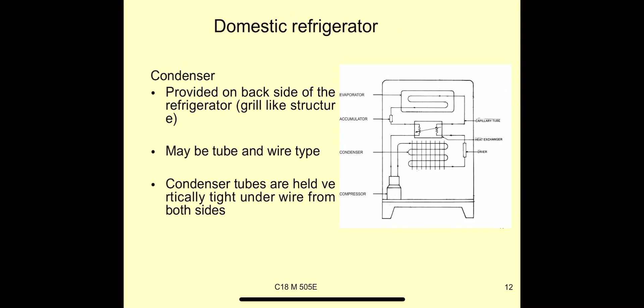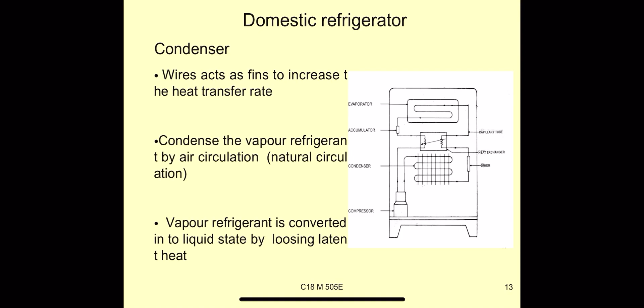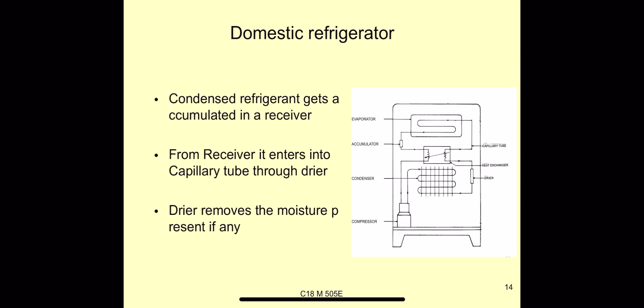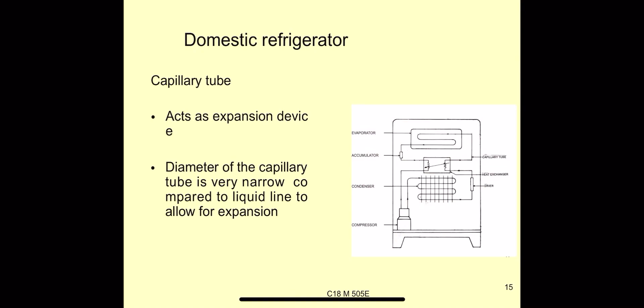The condenser cools the vapor refrigerant by air circulation, maybe natural circulation. The vapor refrigerant is converted into liquid state by losing its latent heat. The condensed refrigerant gets accumulated in a receiver, and from the receiver it enters the capillary tube through the dryer. The dryer removes the moisture present, if any. The capillary tube acts as the expansion device, and its diameter is very narrow compared to the liquid line to allow for expansion.